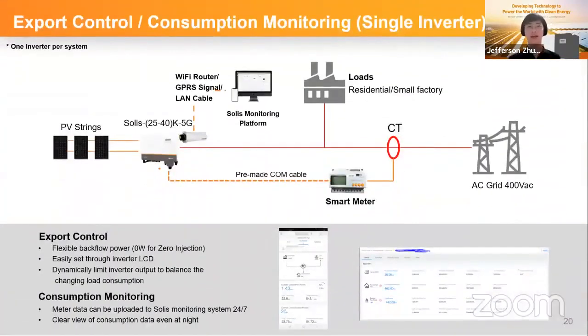Our inverters also support export control or consumption monitoring, depending on the model. For our 25 to 40 series, it supports consumption monitoring and is flexible - feed-back power can be set to 0 or any number you want to input. It's easy to set up through our inverter LCD screen, and all our inverters have a screen. The dynamic input and inverter output limit output based on your house load, so you don't need to worry about this part.